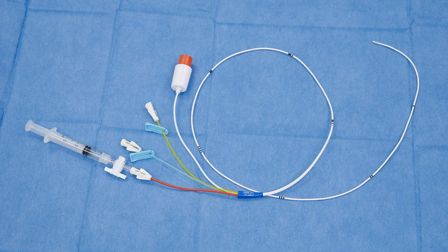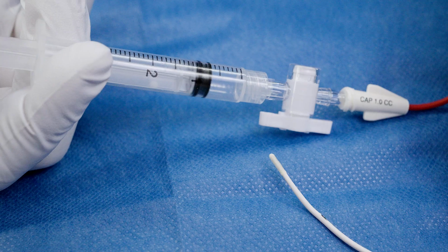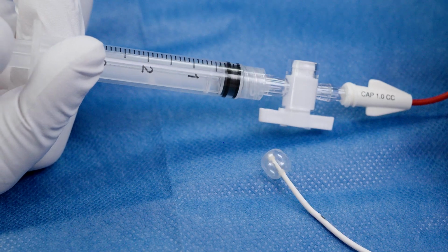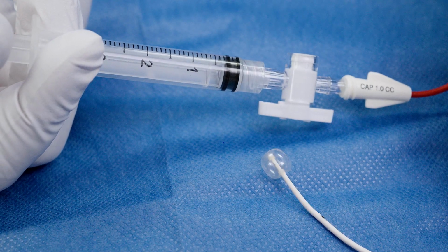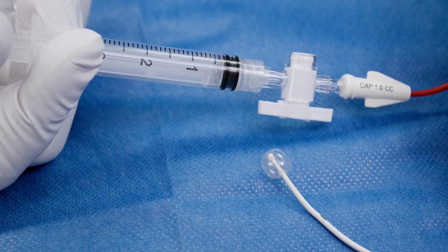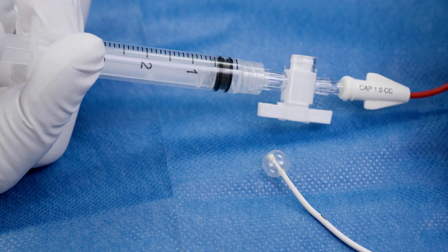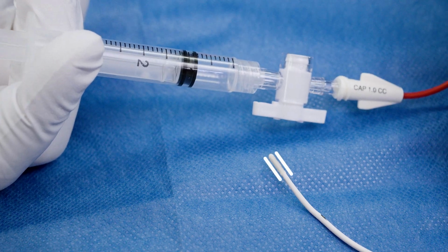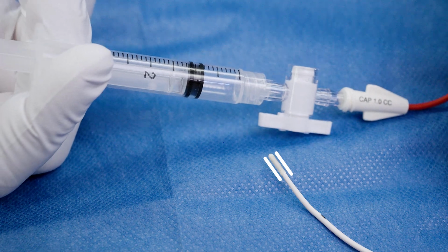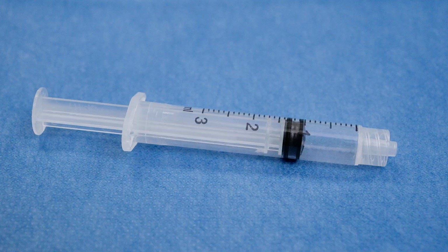The flow-directed balloon thermodilution catheter is made of radiopaque polymeric tubing. The catheter has 4 or 5 parallel lumens that form separate extensions at its proximal end. The balloon inflation lumen has a one-way stopcock at its proximal end and a latex balloon located near the catheter tip. The catheter is tapered under the balloon, so the external diameter of the catheter remains uniform along its length. A controlled stroke syringe is provided for occlusion pressure monitoring.